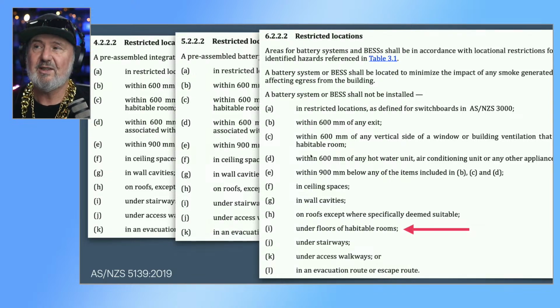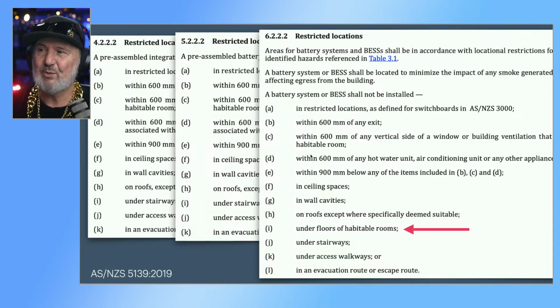Now, restricted locations in Sections 4 and 5, if you look at the clause number at the top there, 4.222 and 5.222 are identical. So your pre-assembled BESS, 4.222, and your pre-assembled battery system, 5.222, have exactly the same restricted locations. But when you get to Section 6, there's one additional point in that list, and it says a restricted location is under floors of habitable rooms.